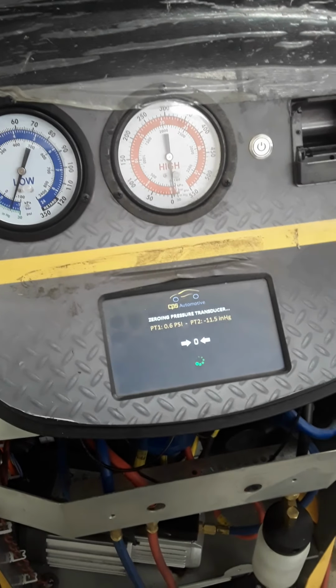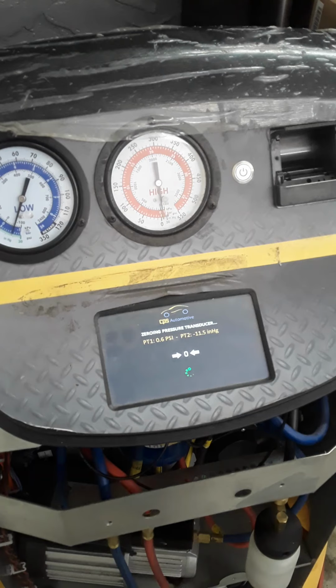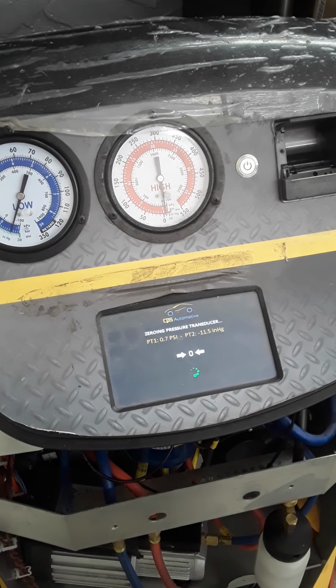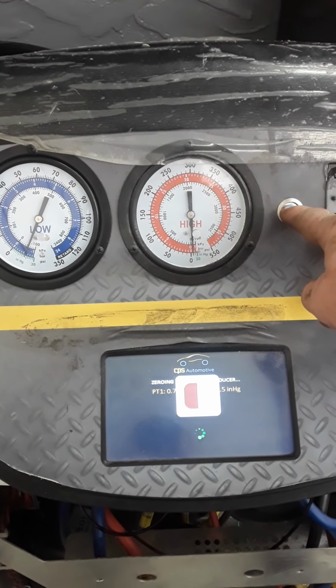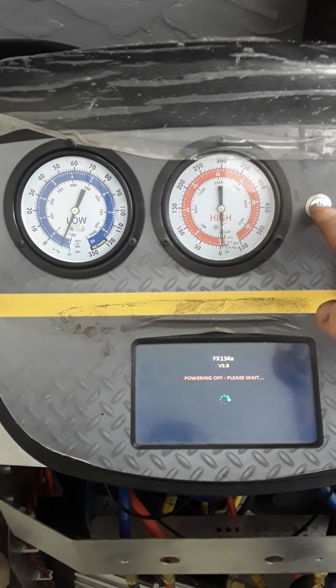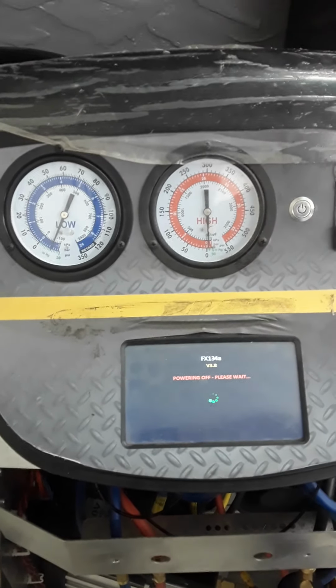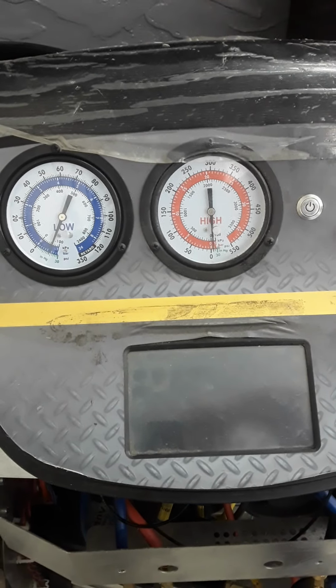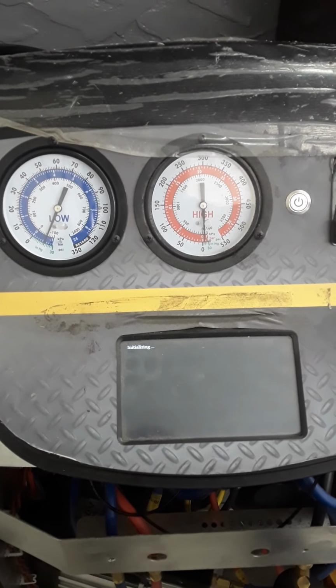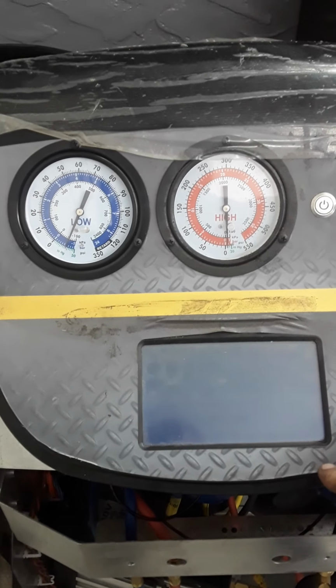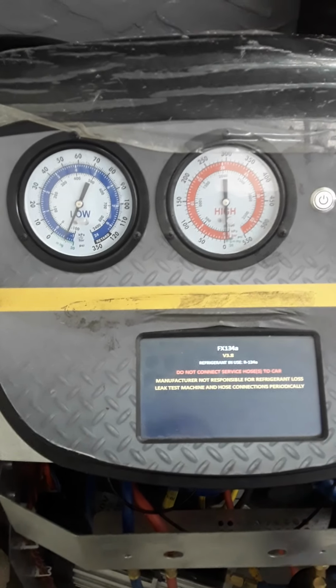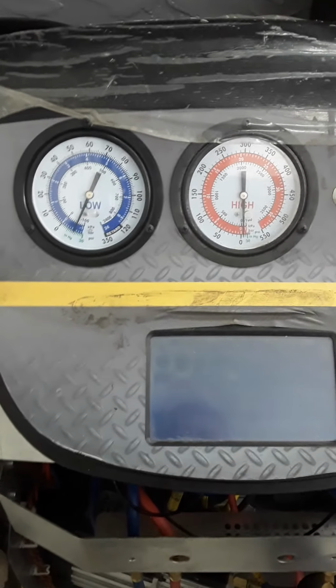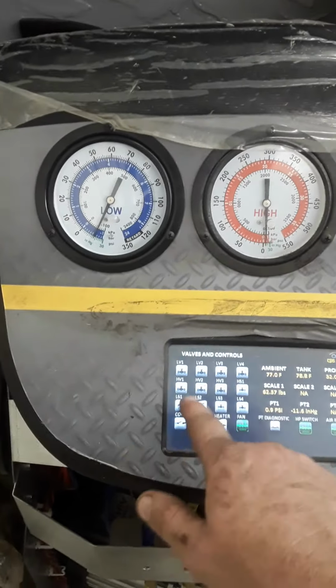Okay, it's at 0.07. PT1. Okay, tell me again, which PT is at 0.07? PT1. Michael, what he's telling me this machine is doing is what I had a machine do. That brass cylinder in PT1, the brass thing with the hole in it? Yeah. Was clogged. And with it being clogged, it can never zero that PT.